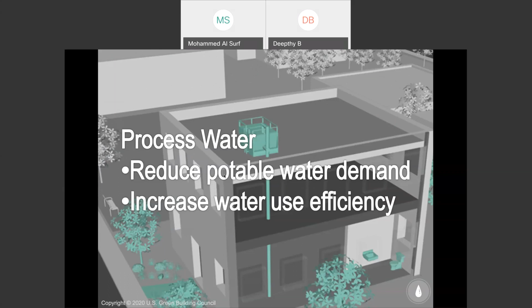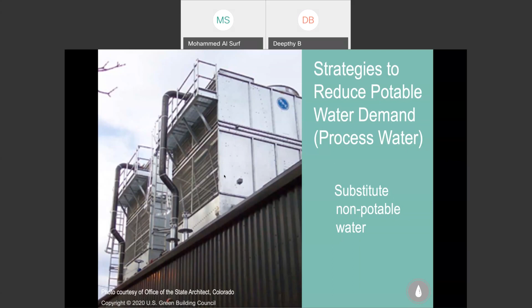The first strategy to reduce potable water demand for process water is to substitute with non-potable water, because we don't need potable water for cooling towers. As with both indoor and outdoor water use, we need to reduce demand by utilizing captured rainwater and non-potable water sources or gray water in cooling towers, chillers, and boilers, and replace evaporative losses with non-potable make-up water. Non-potable water can be harvested from rainwater, air conditioning condensate, or municipal reclaimed water. But again, it's very important to check with your local and building codes.